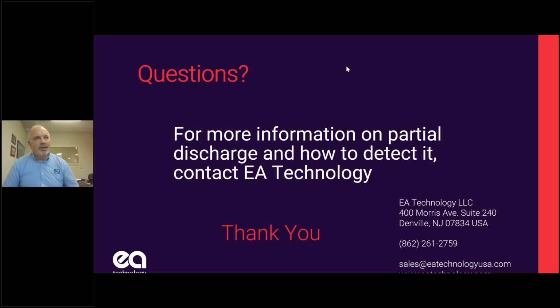It won't be in the coil then. Sorry? It won't be inside. It'll be more in the cable compartment. Yeah, if you have a cable termination box, very often, again, it's a termination, it's where workmanship's taking place. You'll get PD in there, and you can test that with TEV, ultrasonic, or HFCTs.